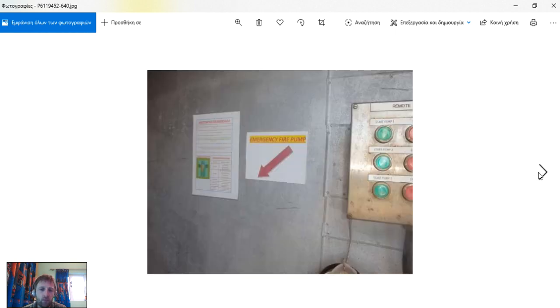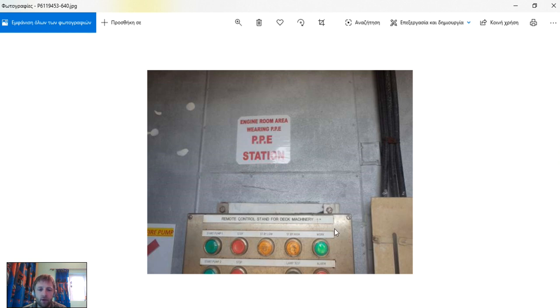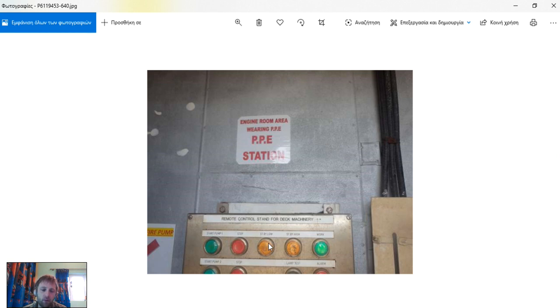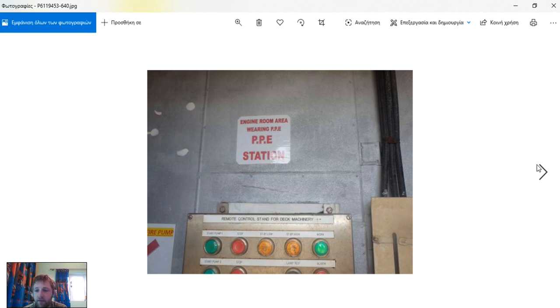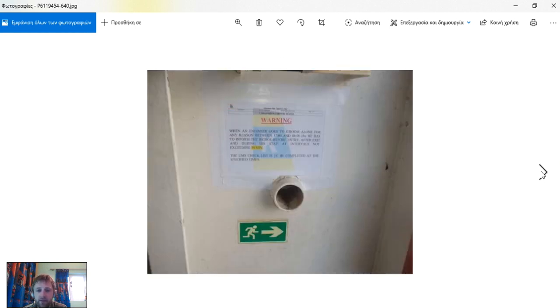It's very good to post PPE there so it will be available. As you can see, there is a remote control stand for deck machinery. The proper way to start: first, before you start, you set to low pressure, start the pump, and then set to high and then to work pressure. Also check the lamp test to verify that all the lamps are working.